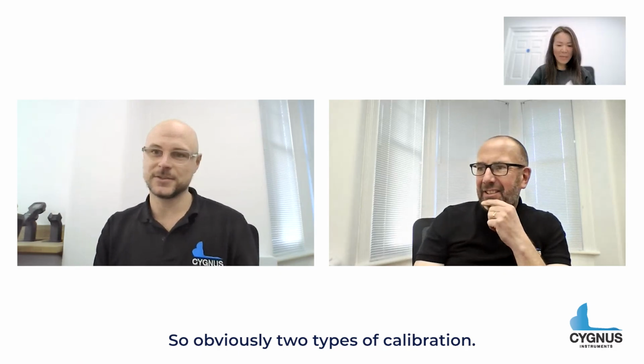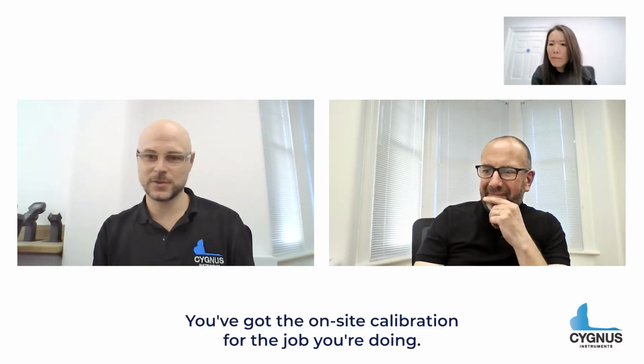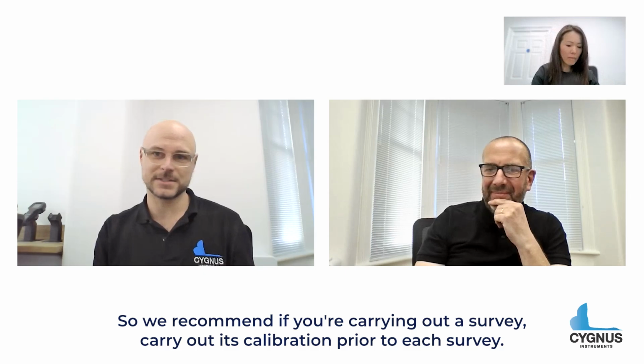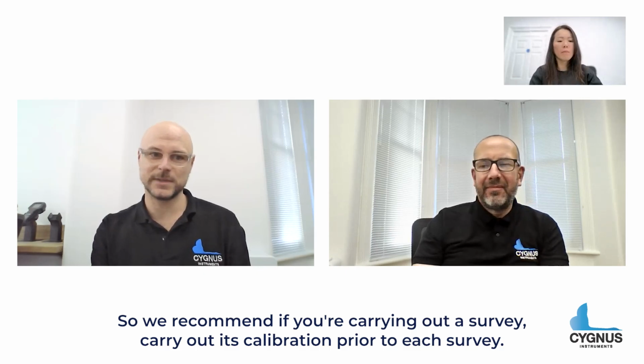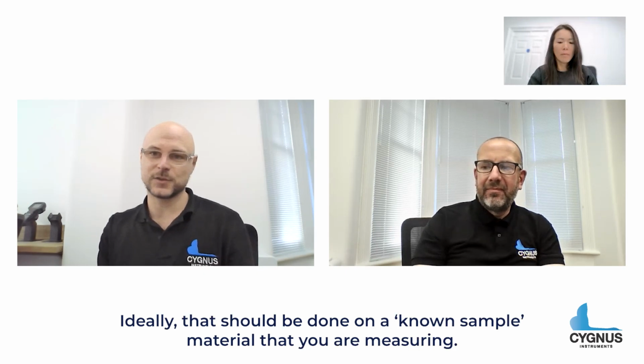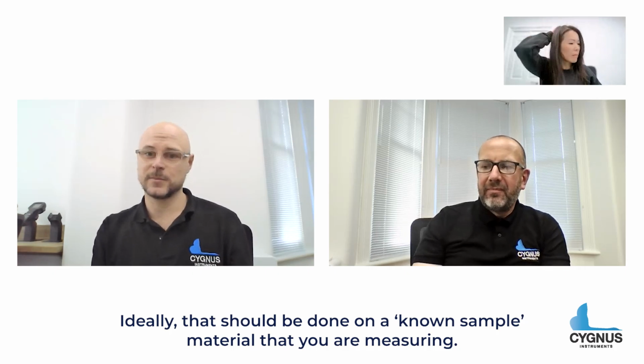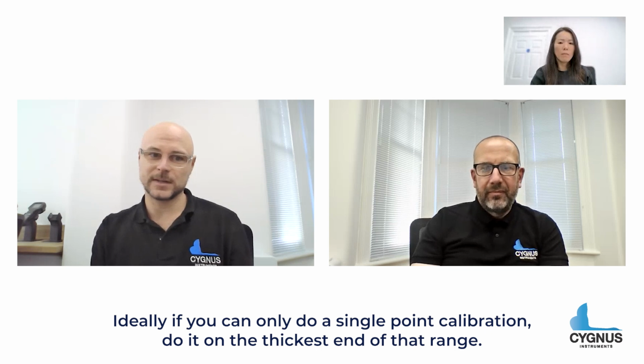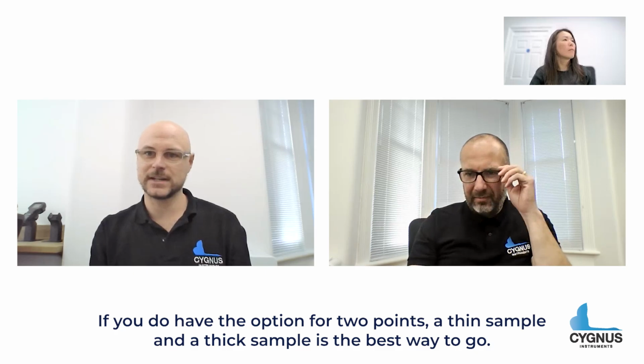The next question is, how often do you recommend calibration? I think Matt, could you help us again? Again, there's obviously two types of calibration. You've got the on-site calibration for the job you're doing. So we recommend, if you're carrying out a survey, carry out a calibration prior to each survey. Ideally, that should be done on a known sample of the material that you are measuring. Ideally, if you can only do a single point calibration, do it on the thickest end of that range. If you do have the option for 2-point, a thin sample and a thick sample is the best way to go.